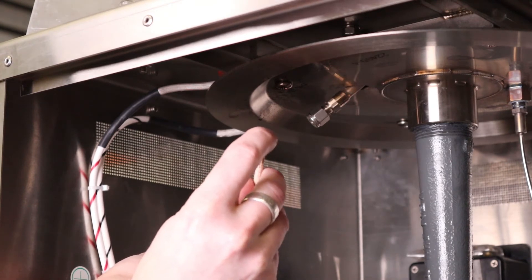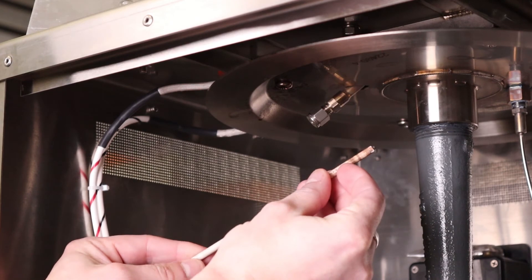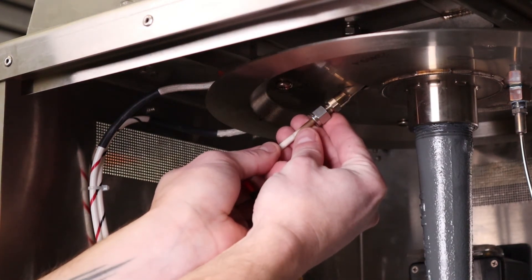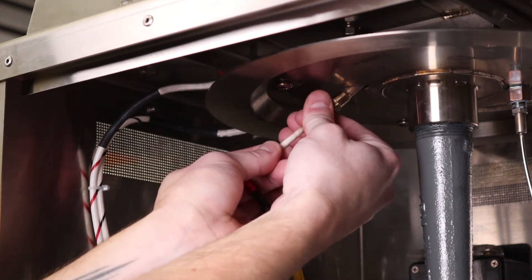Inspect the tip for any wear or any cracks along the insulation. Reinstall the electrode and use the mark you've made as an indicator of where to stop and then hand tighten the fitting.